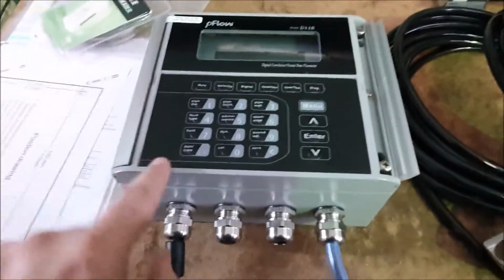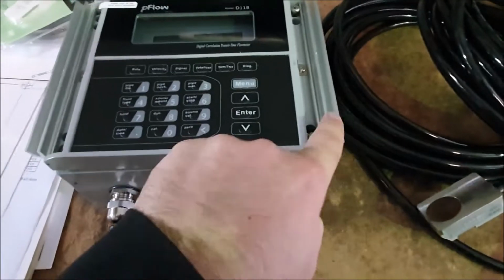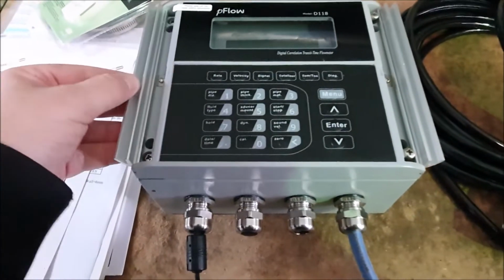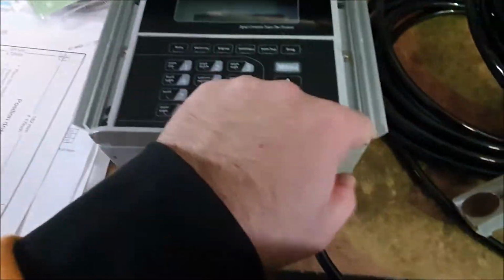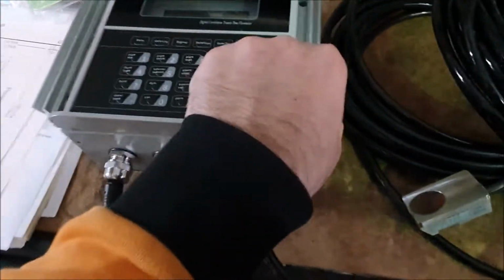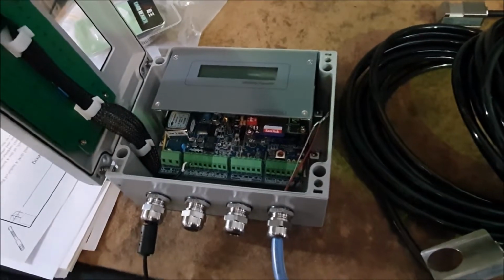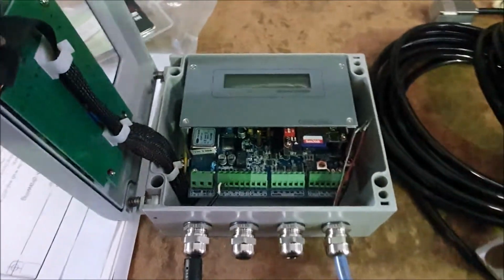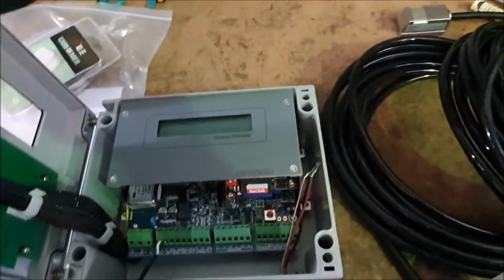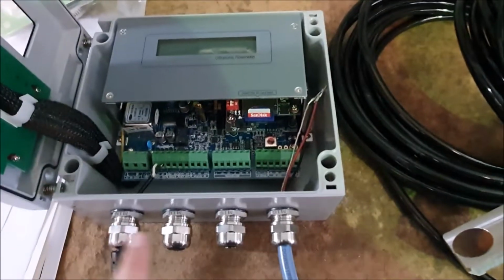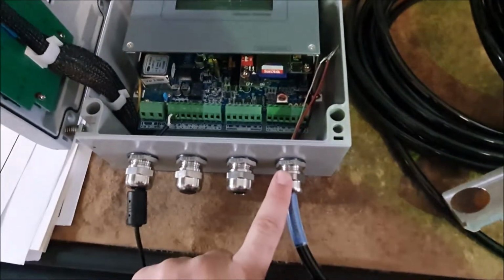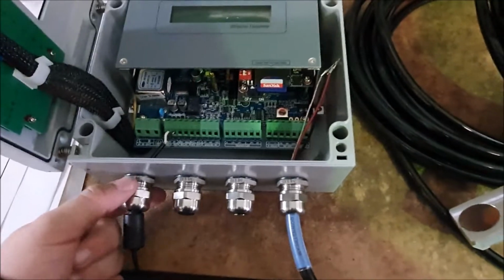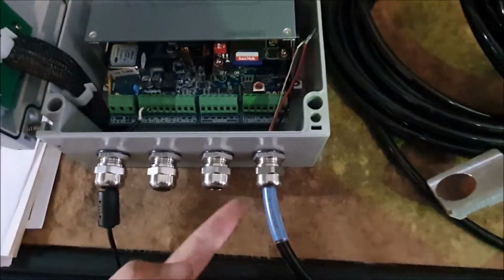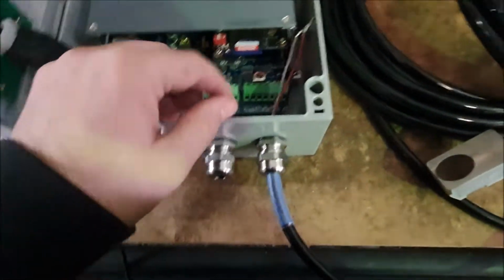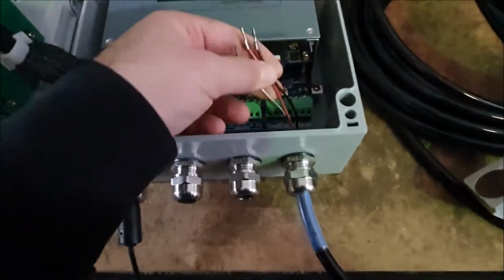Okay, so getting into it, you'll have these flip out covers, and then you'll have a screw on each corner. So just undo each of these, and then the front cover will pivot open. Okay, next you'll connect up your transducers. So in the bottom of the flow meter you've got 4 cable glands. This is just where you'll run through your cables, so it's waterproof, dust tight and everything.